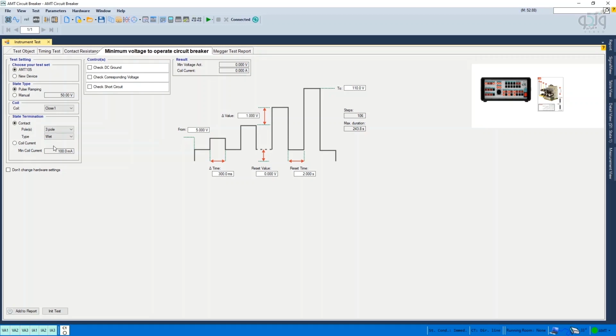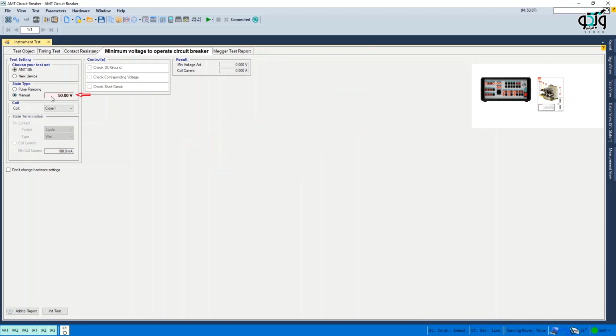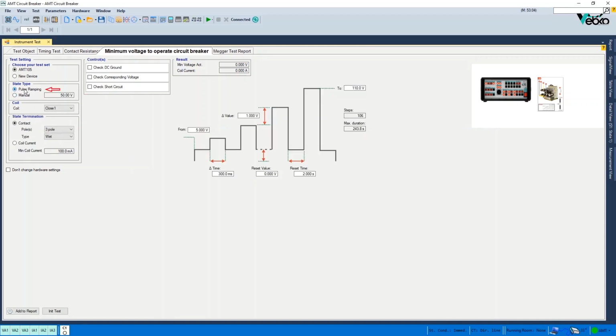In this test, two methods are available to apply voltage to stimulate the bobbin. Using the manual method, you specify a particular voltage and after pressing Init test, apply that to the circuit breaker. But in the pulse ramping method, you can increase the voltage gradually and find the minimum voltage which can cause the circuit breaker to operate. By selecting pulse ramping, a graphic figure is displayed whose different parameters must be specified. Let us explain this with an example.